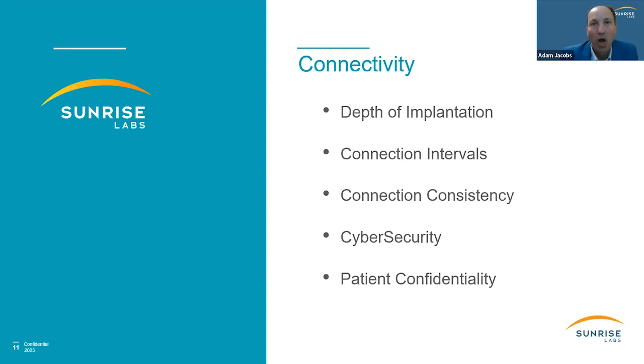The connection interval is how often you'll talk to your external device, and obviously less is better for battery purposes. Connection consistency is something to consider, because you can't rely on cell phones or Wi-Fi to always have a connection to your server, and you can't rely on the phone always being there for the device. So you need to architect your system such that the device can operate safely and perform its functions without that connection, and then have ways to recover when the connection is actually made. Sometimes that means throwing data away. If you go off to the desert for a month on vacation and then come back, you might not have enough storage to store all that data if you're storing some kind of streaming data.